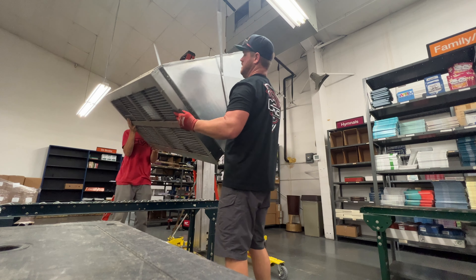We are ready to get this unit hung. The brackets up there are not level — the front is higher than the back — so the all-thread coming down won't be perpendicular to the floor, which would make the unit not hang level. What I did was get all my all-thread cut to size and used my Hilmor bender with a half-inch to bend what I needed so the all-threads come down nice and level. That should make the unit sit perfectly level without any issues.